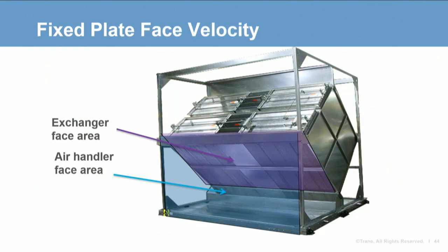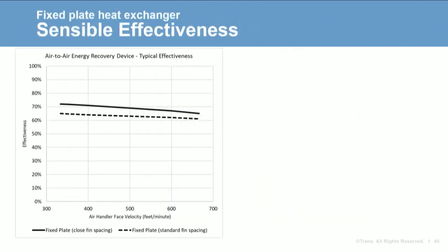In these examples, the fixed plate heat exchanger is set at an angle, meaning the heat exchanger face velocity will be lower than the air handler face velocity. For example, a 500 feet per minute air handler will have an exchanger face velocity between 350 and 400 feet per minute. Sensible effectiveness for a 10,000 CFM fixed plate is generally between 60 and 70%. The slope of the effectiveness lines doesn't decrease as rapidly as other technologies — sizing and plate spacing have the largest impact on effectiveness, while face velocity has lesser impact.